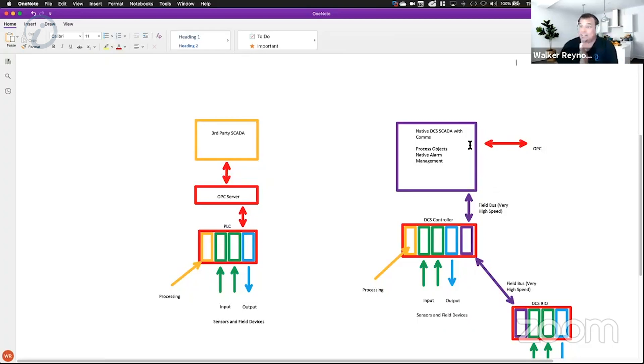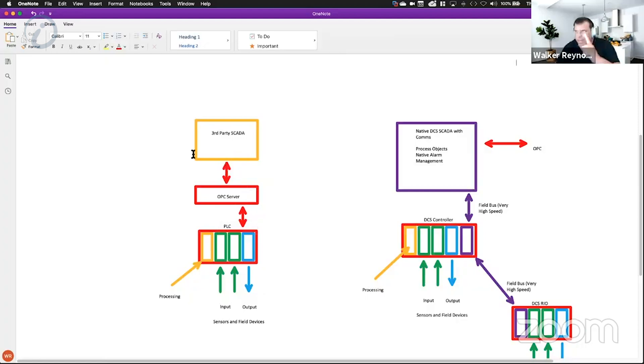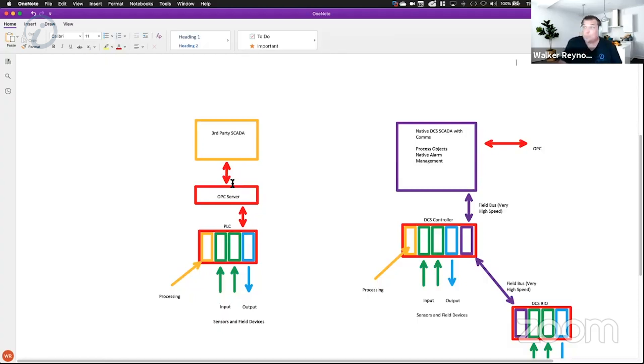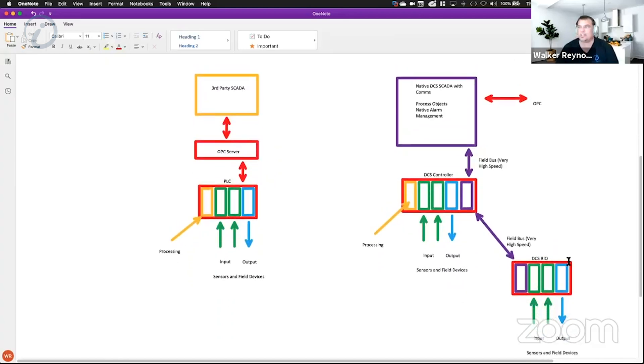On the right-hand side I have DCS — this is the comparison to the PLC/SCADA structure. One thing to point out: the PLC connects to the OPC server over Ethernet/IP, and the third-party SCADA software also connects to the OPC server over Ethernet/IP — it's an open, regular Ethernet/IP network. DCS, on the other hand, cares about two things above all else: security and speed.